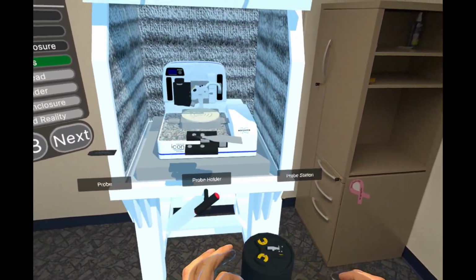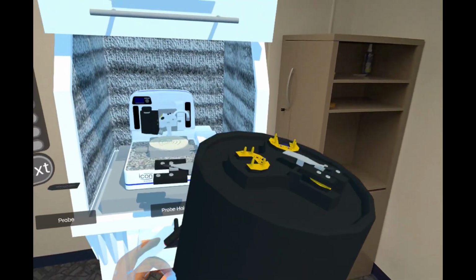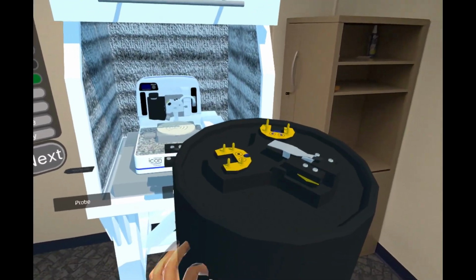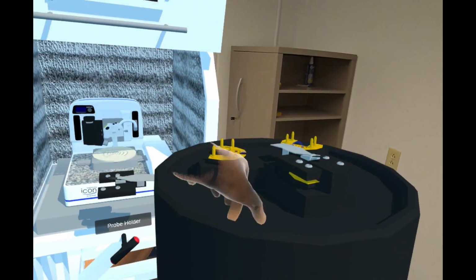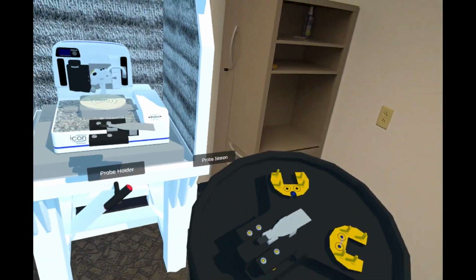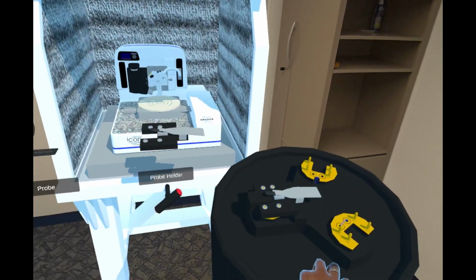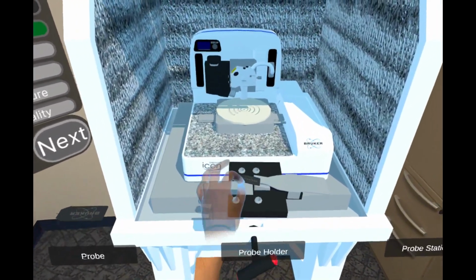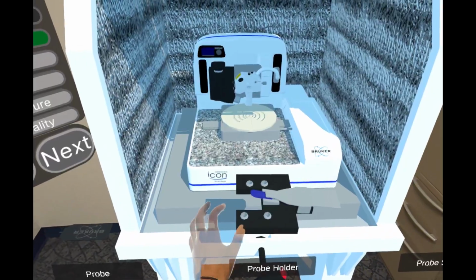There are tiny little cutouts in the back of the probe holder channel. These are for the tweezer tips to come in and grasp the probe when you're removing it. When manipulating AFM probes, it helps to stabilize your hand by resting your arm on the table and several fingers on the probe station side for balance to help reduce shaking.